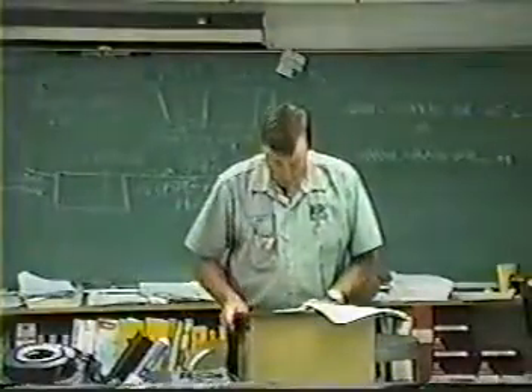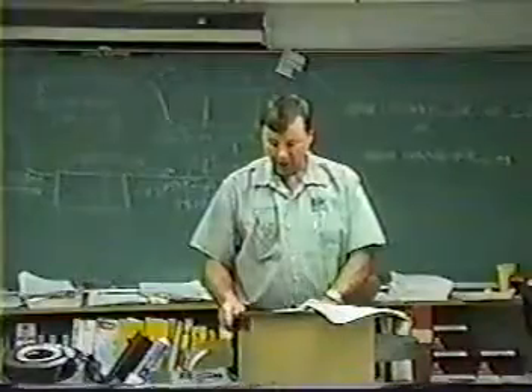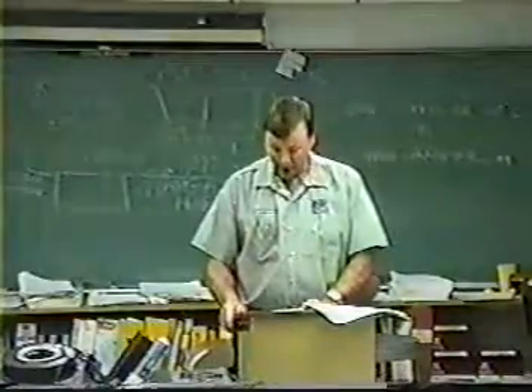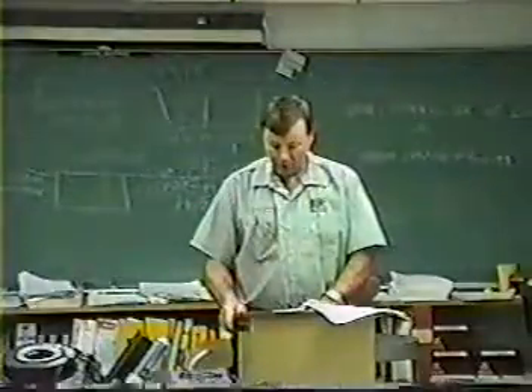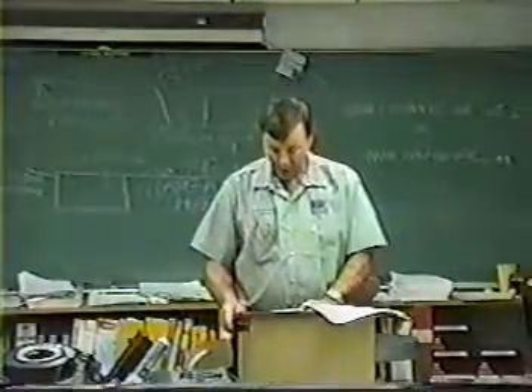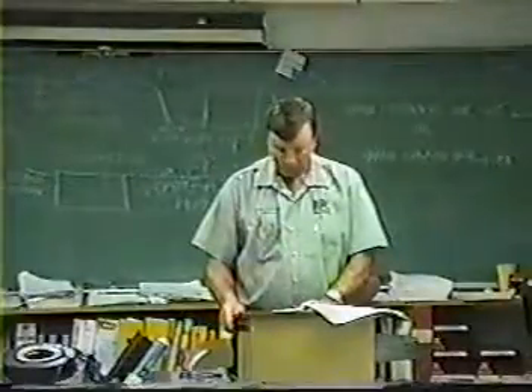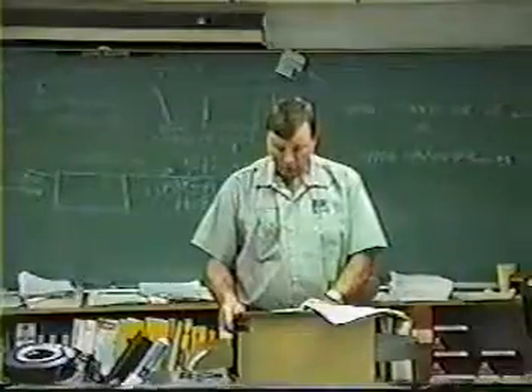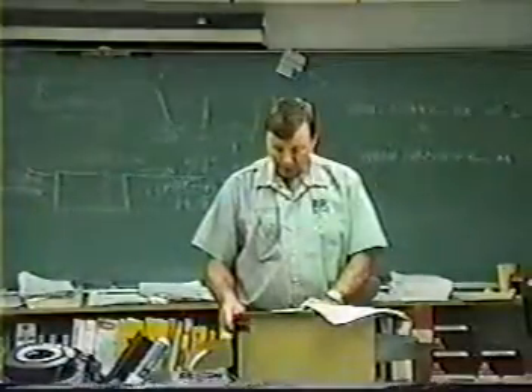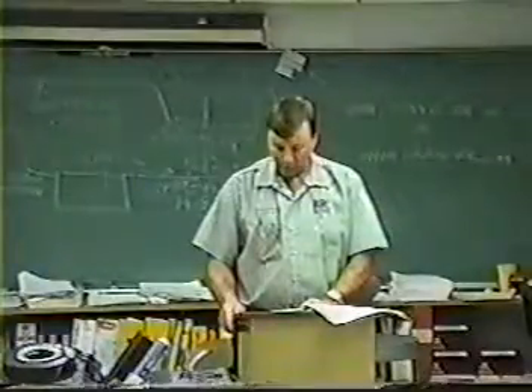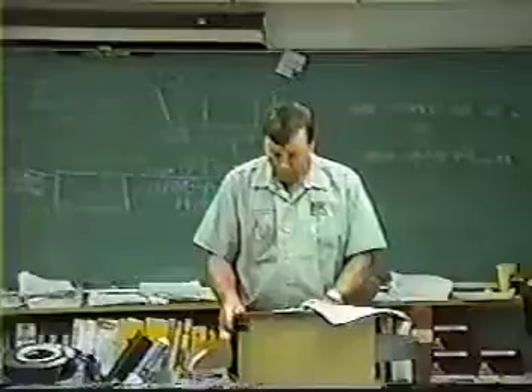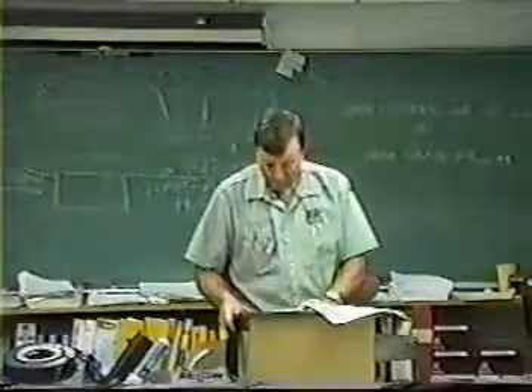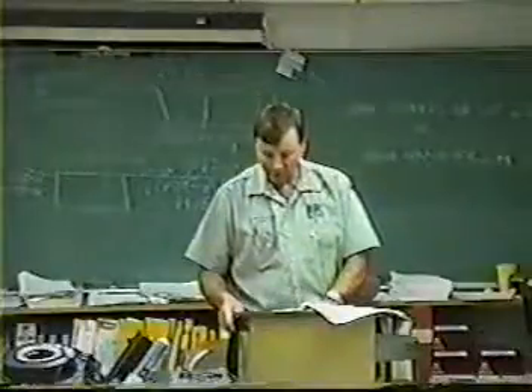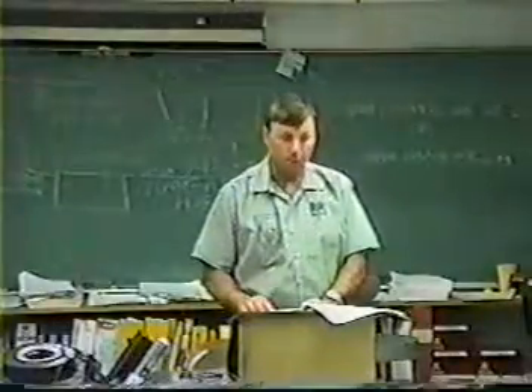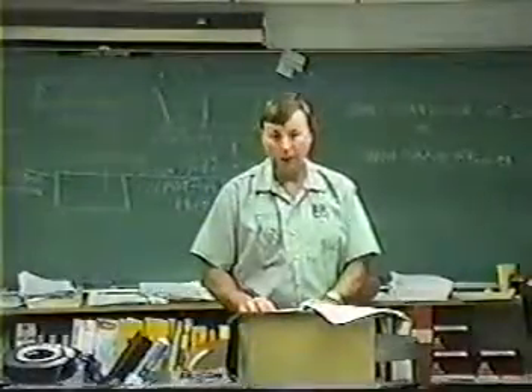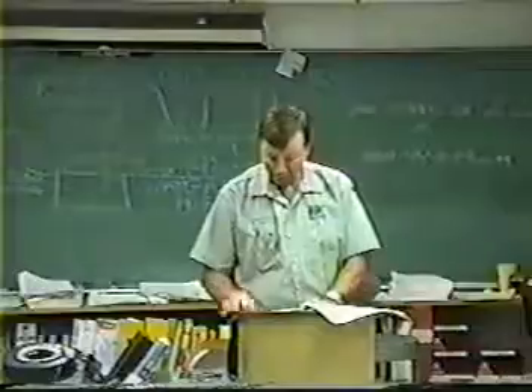Recovery devices. Refrigerant recovery and or recycling equipment manufactured after November 15, 1993 must be certified by an EPA-approved equipment testing organization such as UL or ETL to meet ARI standards. There are 2 basic types of recovery devices: system-dependent or passive, which relies on the compressor within the refrigeration appliance to recover refrigerant, and you can only use those on appliances containing 15 pounds of refrigerant or less. The other type is self-contained or active, which has its own means of drawing refrigerant out of the appliance, which is what you basically use on the job today. You will be using the active type.